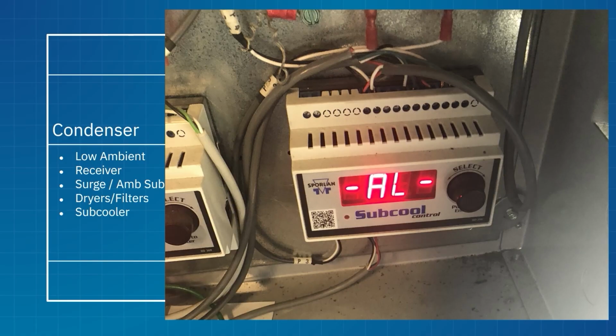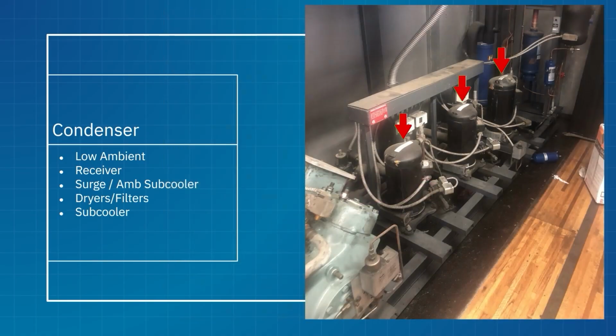All right, what have I got going on here? I got the green compressors and I got the black compressors on the same rack. So this, if I find this setup, this is my satellite setup. I've got a low temp or a medium temp rack, and I want to run a different suction group, but share discharge and liquid. Same condenser, same subcooler, right? But after our liquid goes through the expansion devices, they come back to different suction headers. Okay, that's my satellite, nothing unique there.